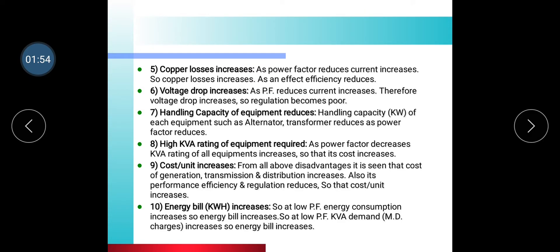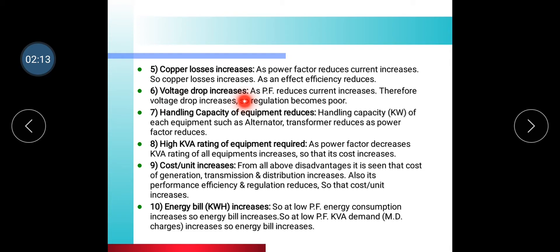Copper losses increase as power factor reduces and current increases. Efficiency reduces as a result. As power factor reduces, current increases, and therefore voltage drop increases. Increased current and voltage drop leads to poor voltage regulation.